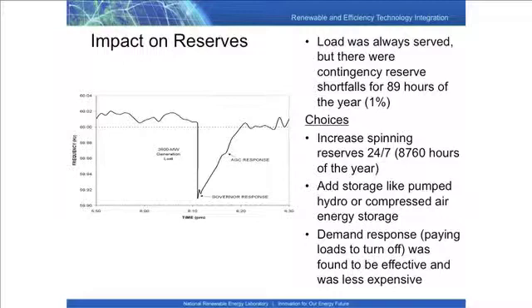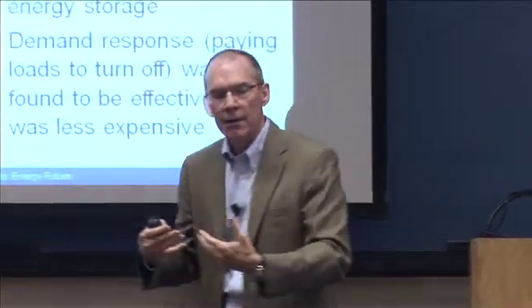Impacts on reserves: this is an interesting graph of the ERCOT system showing the need for reserves. This is the frequency, showing what happened when two nuclear units tripped offline at the same time, losing 2.6 gigawatts of generation. That causes the frequency to take a dive, and they have to recover from that, or there's a cascading effect in the system and you have a blackout. So this is why you need reserves online.